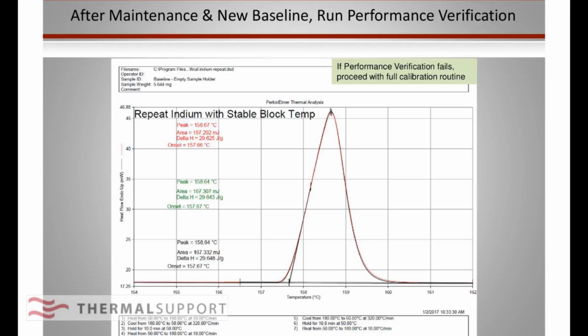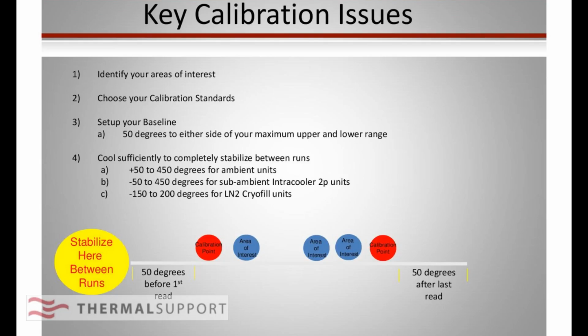Again, you saw this in the previous video. Repeat indium with a stable block temperature. This thing is dead on. We've got reliable numbers. Now we know the instrument's working right. Now we want to calibrate it. So let's go on over to the calibration issues.